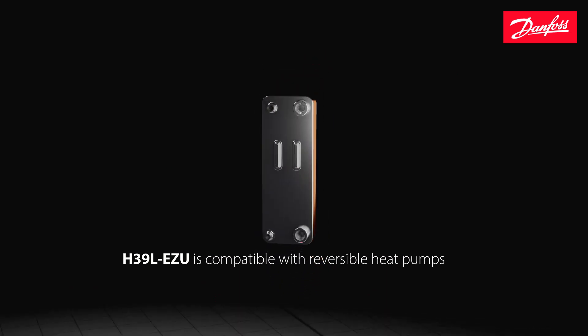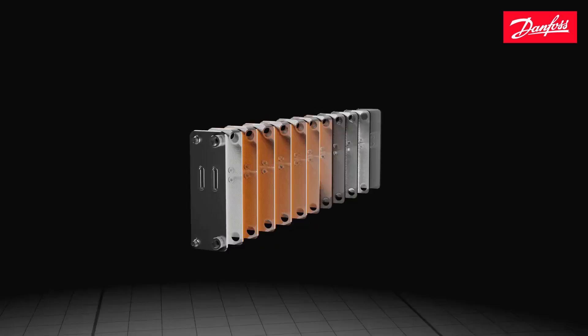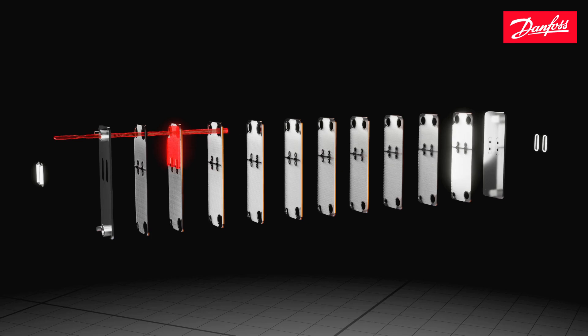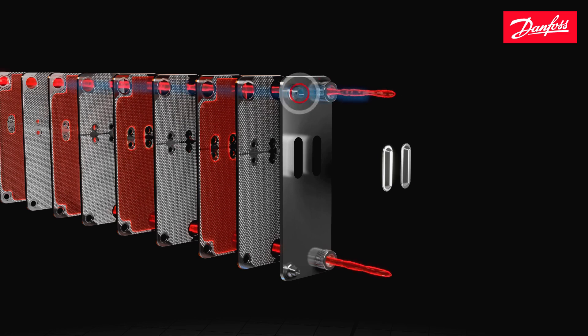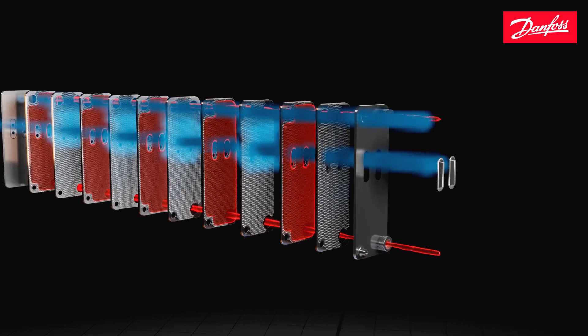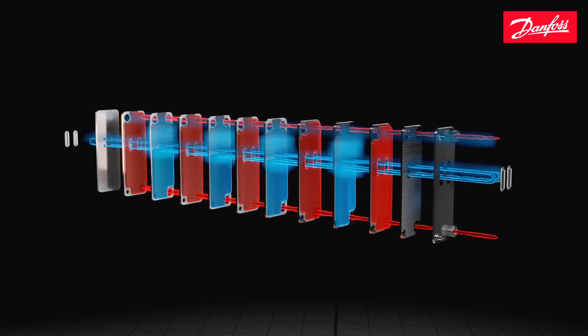Fully compatible with reversible heat pump systems, the H39L-EZU can also operate in condenser mode. The brine water flows in through the water side inlet and passes through the heat exchanger before flowing out of the water side outlet. The vaporized refrigerant then enters the refrigerant side inlet and condenses back into liquid form before exiting the heat exchanger through the refrigerant side outlet.